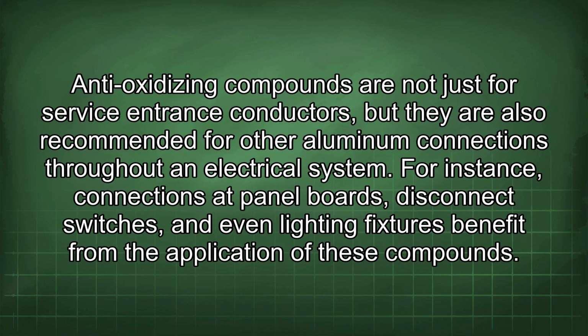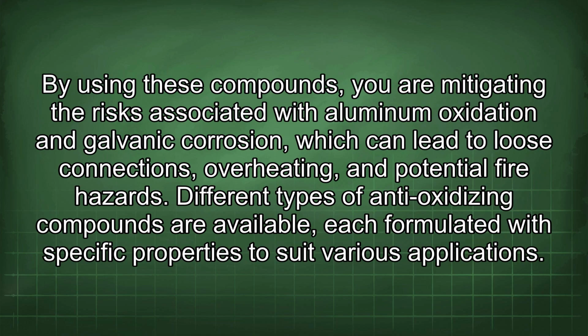Anti-oxidizing compounds are not just for service entrance conductors, but they are also recommended for other aluminum connections throughout an electrical system. For instance, connections at panel boards, disconnect switches, and even lighting fixtures benefit from the application of these compounds. By using these compounds, you are mitigating the risks associated with aluminum oxidation and galvanic corrosion, which can lead to loose connections, overheating, and potential fire hazards.